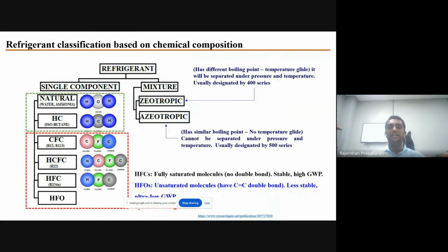On the other hand, there is mixing of one component of refrigerant with another one, like mixing of HC with CFCs, or mixing of HFCs and HFOs, or mixing of natural refrigerants and other synthetic refrigerants. It can be categorized into two types: zeotropic and azeotropic. Azeotropic means that the different components in the mixture have a similar boiling point. There will be no temperature glide, and it cannot be separated during condensation and evaporation. Usually, these refrigerants are designated by the R500 series. On the other hand, zeotropic mixtures have different boiling points among the components and show very high temperature glide. These refrigerants are designated by the R400 series.